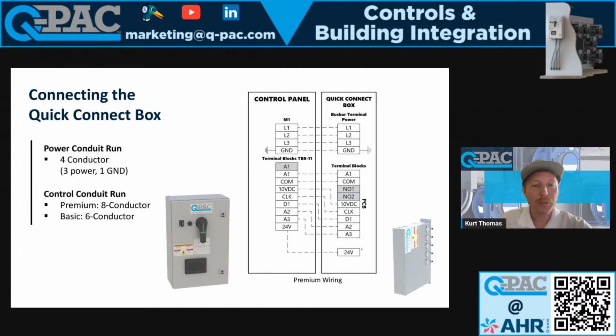Like I mentioned earlier, connecting between the control panel and quick connect box, 8 conductor wire, use separate conduit. You can use any type of control wire you typically have on your truck, right? It can be anywhere from, I think, 14 gauge up to 22 gauge. It doesn't have to be shielded. If you want to shield it, that's fine. Just make sure you don't ground the shielding at both sides, right? Make sure you ground it at one end so you reduce any of that inductance. But it's really that simple. For the basic quick connect box, if you get a basic package, you will not get the HMI and the PLC, but you still will get an HOA switch and a potentiometer and your disconnect switch. It's just going to be a lot more limited as far as controls. So with the basic, you would run a 6 conductor wire.